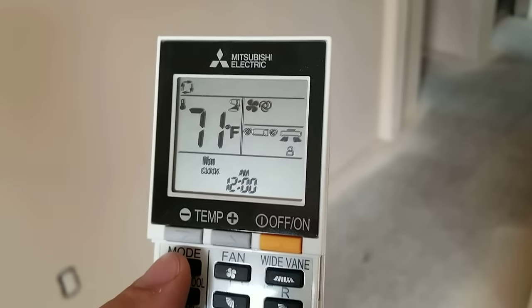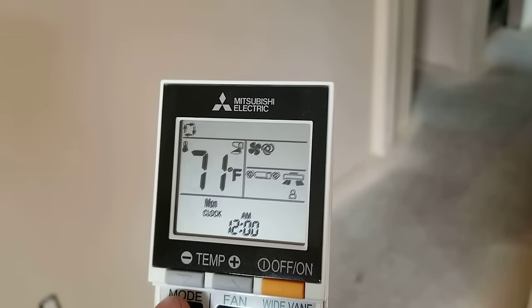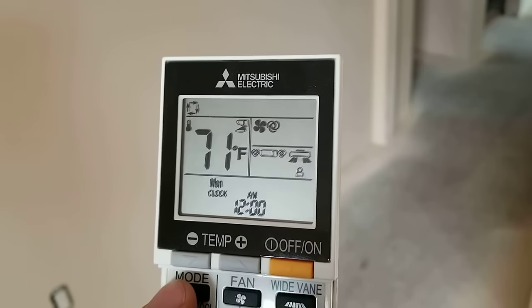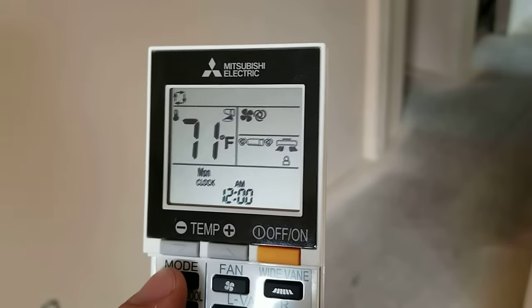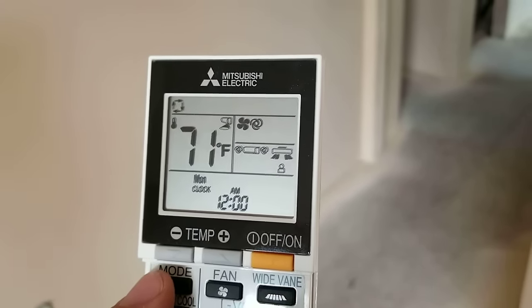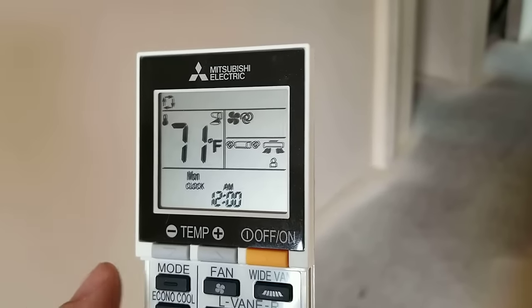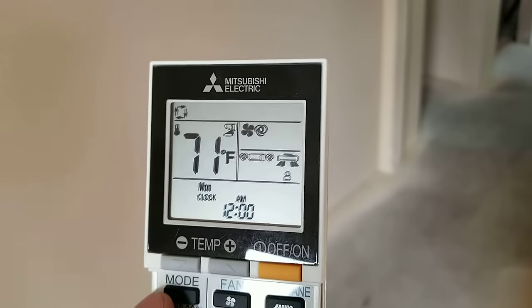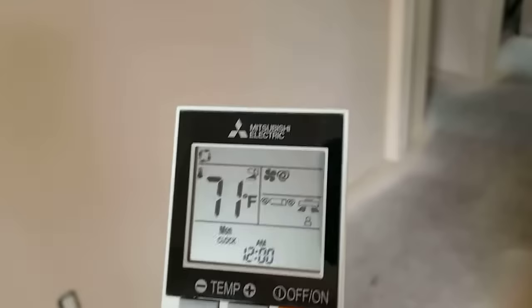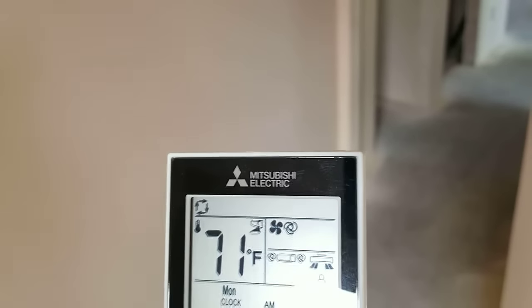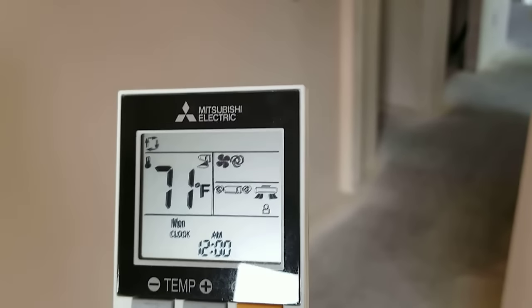In this case, the unit can go all the way to 75 and a half degrees before it will start cooling or your room temperature might fall all the way down to 66.5 degrees before it starts heating. So for most of us, that's not comfortable.